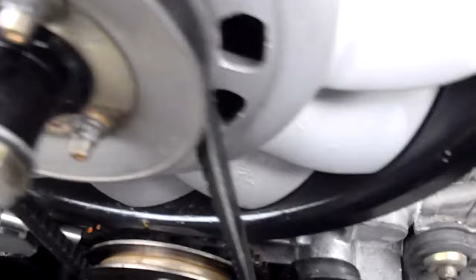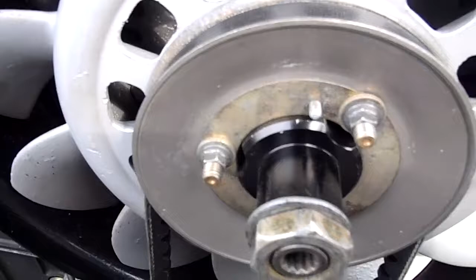Here's the fan belt. Fan belt is a size 10 by 725. There's one shim out here. In order to tighten the belt, you would remove shims from in between each pulley half and put them on the outside here. Vice versa, to loosen the belt, you would put the shim that is out here in between the 2 pulley halves.